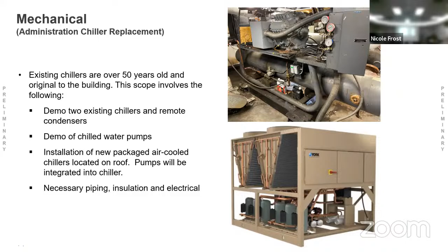There are condensers out on the roof. We're looking to eliminate the condensers and the chillers inside the building, demo those out along with the pumps, and install two packaged chillers with pump packages out on the roof, including all the structural steel that goes with that, and piping back into the penthouse where the piping is now. It's detailed work, but definitely a needed measure to get more years of life out of this building.